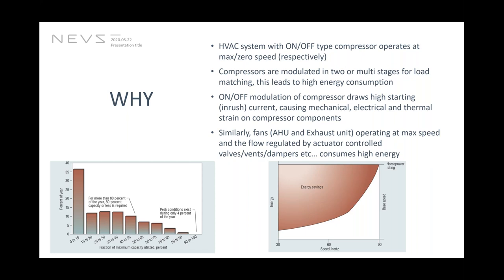So basically the peak power point, and then regulate the compressor pressure as well as airflow, just basically wasting this whole region of this orange region, simply by not controlling the speed. And yeah, this shows that there is a greater potential of energy saving if we have a very fine modulation or control of the speed of the electrical motors used in the HVAC system. This can be replicated in other industrial processes as well. But HVAC system is a great example to demonstrate.